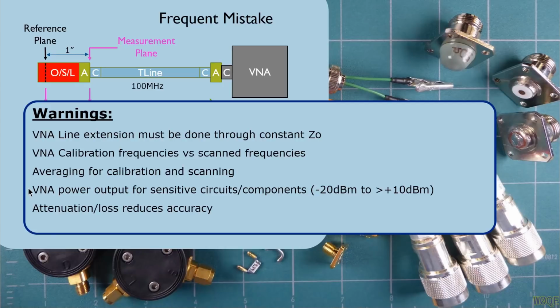This is a warning, and everyone should be aware of this: the analyzer puts out power. This analyzer puts out power to make this measurement, and if you have a very sensitive circuit out here, you could hurt that circuit. Different analyzers put out different power. My 4170 puts out minus 18 dBm. My 2180 puts out plus 6, although it's adjustable, and this is the typical range for most VNAs.